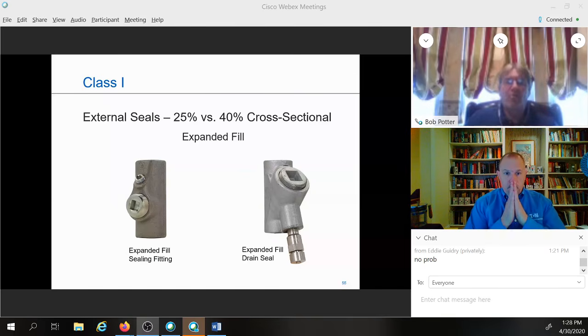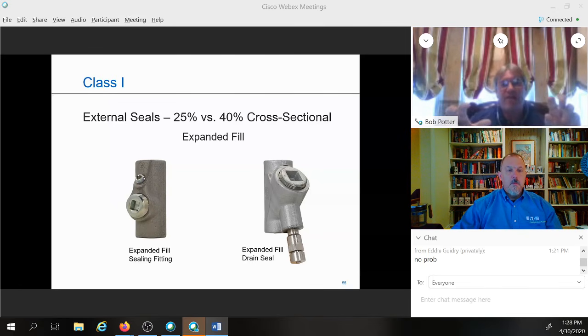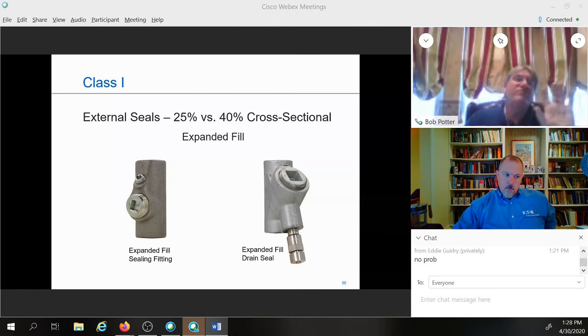Okay. And that starts to go a little bit with what we were just discussing. The first part of the code will tell you that you have to take off the jacket and separate the conductors. But then it goes into an exception where they allow you to use the approved sealing method within the enclosure. And again, the code just says approved sealing method. That's why I recommend using the same epoxy that works for the cable gland seal to prevent or minimize the gases from migrating through the cable core. And then once you do that inside the enclosure, you've stopped the only place where the gas can enter the cable core. It's pretty much like you dammed the beginning of the tunnel. And so now you have this jacketed cable that gases aren't going to be able to permeate, and you can run that cable through the sealing fitting as if it was a single conductor.